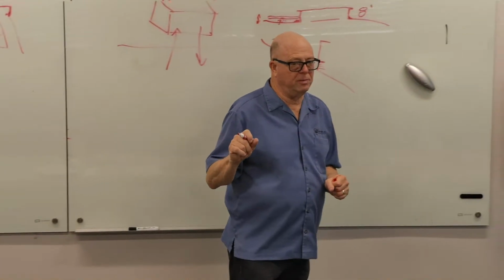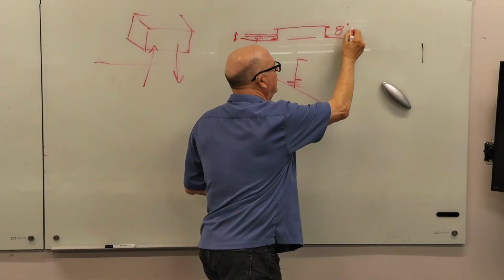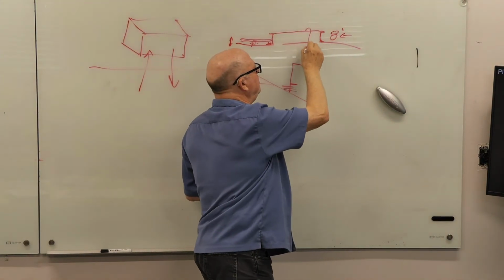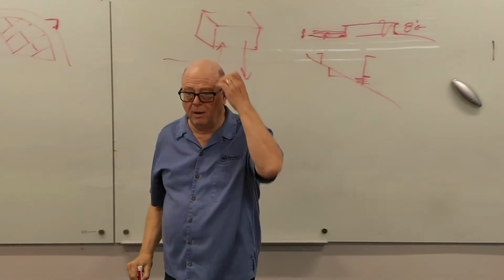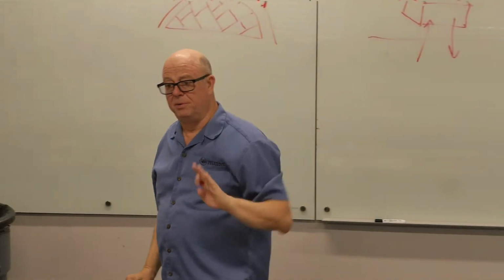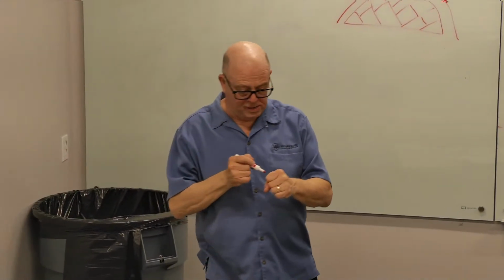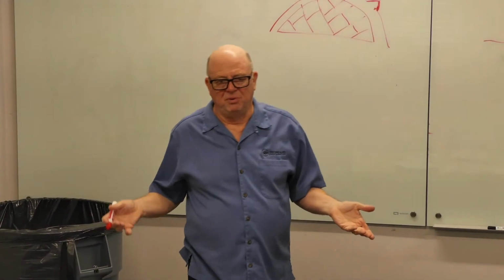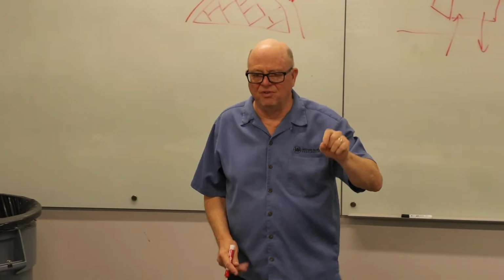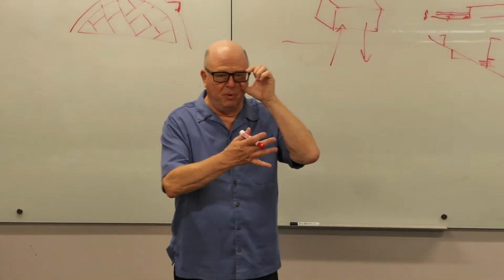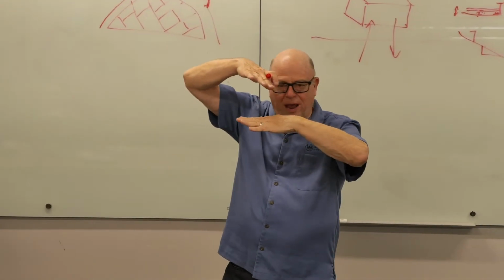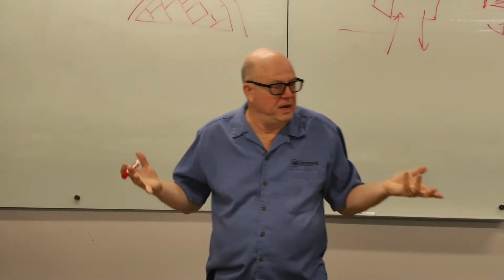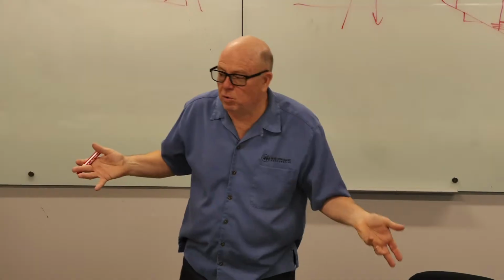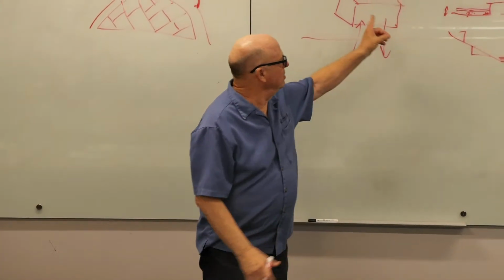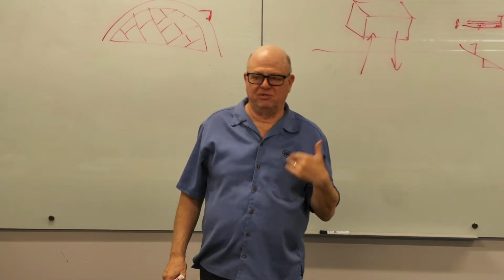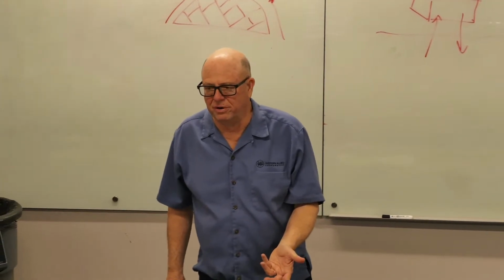Now, I left out something in this height issue. What kind of a P-trap am I going to need, and how much distance do I need for my P-trap to be able to drop? If it's a little 5-ton rooftop unit, there's probably not enough static involved. You guys kind of remember from our previous conversation how deep the trap needs to be, and it's based primarily on how many inches of static we're going to do. Well, for a little bitty package unit, that's probably almost not a consideration.